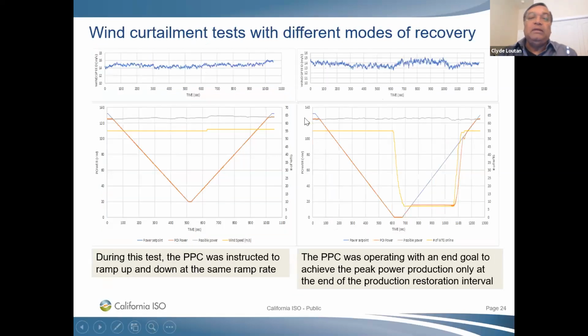Just running into the test, on the left-hand side it shows active power control, where we were able to ramp this unit down from roughly 130 megawatts to 20 megawatts and back up at a constant ramp rate. So again, when you look at this, you can see how well a wind plant could follow a dispatch instruction from the control entity.